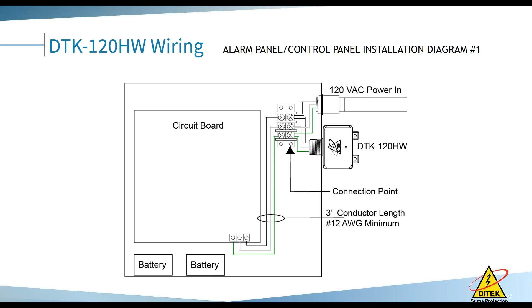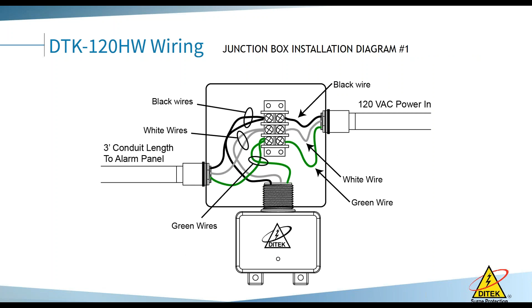Because people say, why don't you give me 3 feet leads on the HW? It's not how long my leads are, it's where it connects to the hot, neutral, and ground, or to any circuit for that matter. From that point, it needs a response time built in. Which is why a lot of times we'll say put it in a 4-square above the panel, maybe 4 or 5 feet away if you want to use this device. Or throw it on the breaker that feeds the FACP. That's a nice clean way.